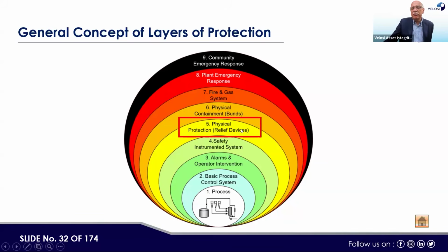And in between, even if the ESD system does not work and the alarm is not attended, there is one mechanical equipment installed, which is the fifth layer of protection: these PSVs and PRVs or rupture discs. This equipment may open and high pressure can be released to the atmosphere, to the flare system, or to the burn pit system. Then if this also does not work, for example on the tank side, there are bunds, where in case of any equipment fluid release, that fluid can be accommodated in the dikes or in the drainage system. Along with that, there is a fire and gas detection system.